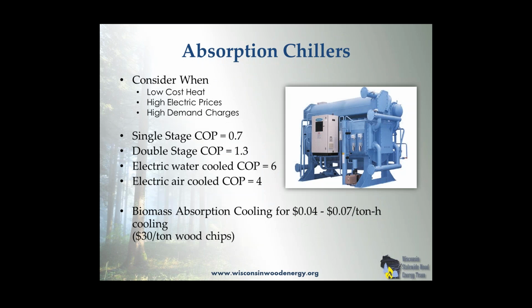Again, absorption chillers, I gave you that example at a hospital. One thing that's not great about absorption chillers, unless there's some other benefit, for instance, unless you get a substantial savings on peak demand charges where you have very high electric charges, they generally don't pencil out. The reason is that a single stage absorption chiller only has a coefficient of performance of 0.7.